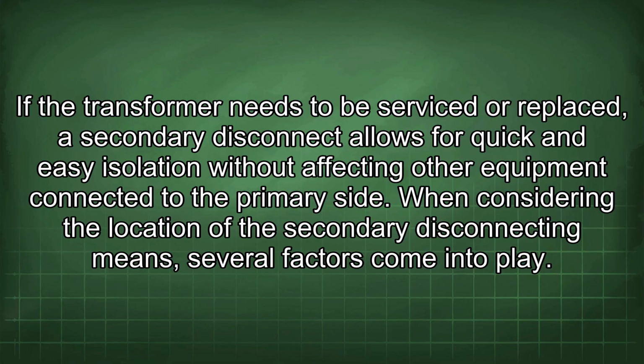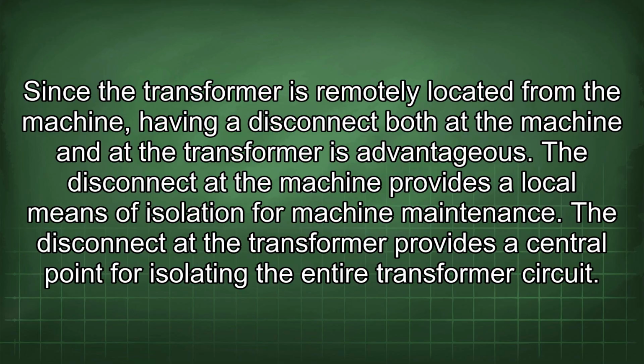When considering the location of the secondary disconnecting means, several factors come into play. Since the transformer is remotely located from the machine, having a disconnect both at the machine and at the transformer is advantageous.